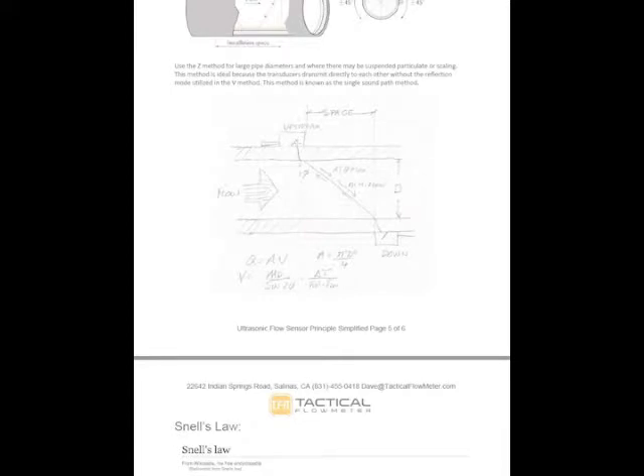This is a 1 megahertz pulse. It's got a little 45 degree angle. Snell's law takes the shortest route in the steel or whatever it is. And then within the pipe, let's say it's water, the acoustic wave travels down. This transducer senses how long it took to go from ping to ping. Then this one goes ping, and this one goes pong, and it tells what the distance is. So what we're doing is measuring the time of flight from this transducer to that transducer through this medium.